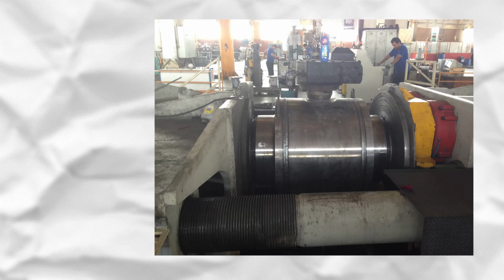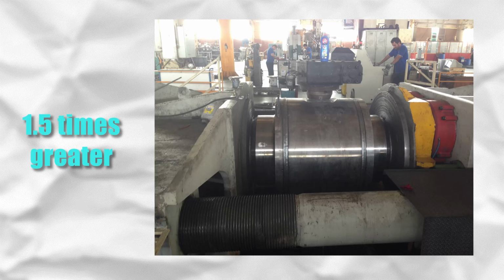The outlet of the positioner carrying the pressurized control air is introduced to the actuator. You need to bear in mind that to supply a control valve, some tests must be carried out by the manufacturer and the results of each are reflected in a report. The first important one is called the shell test, in which the valve is partially open and the pressure of the test is around 1.5 times greater than design pressure. Leakage class test, function test, and backseat test are some other types which are necessary for a control valve.